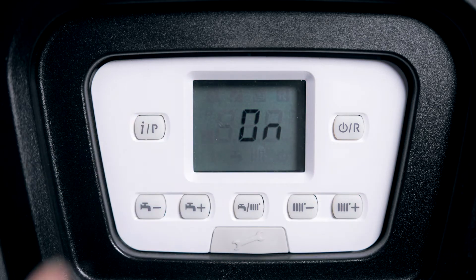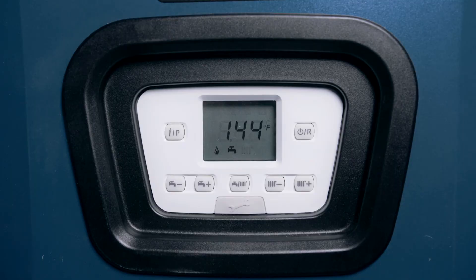The AI control recognizes the type of fuel being supplied — natural or LP gas — and automatically makes the necessary adjustments. No orifice changes are necessary. After initial commissioning, the AI control continuously monitors combustion and self-adjusts the gas and air mixture to optimize burner performance and efficiency. This technology saves energy and lowers utility cost.